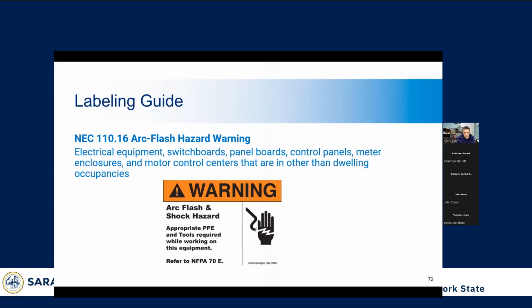So here you have the traditional arc flash hazard warning. This is required on electrical equipment, switchboards, panel boards, control panels, meter enclosures, and motor control centers that are in other than dwelling occupancies. Again, this is obviously a very important warning label. Arc flash incidents can cause death or serious injury, so you want to make sure everyone's aware of that.